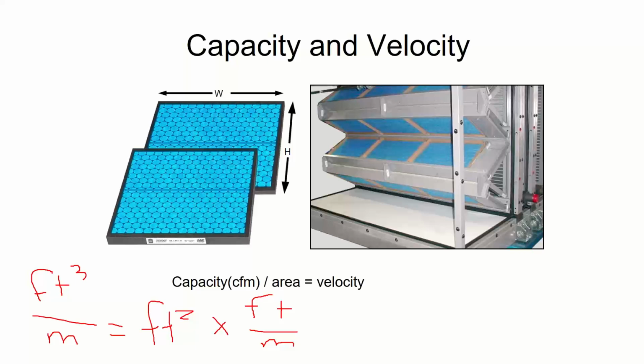So I have a lot of speed and direction going down that tube with the straw, and that gets converted to velocity pressure, which will shove that spitball way out of there, right? But if I put that spitball in a very large tube instead of a small straw, I'm not going to be able to generate that velocity pressure because there's more surface area to work with.